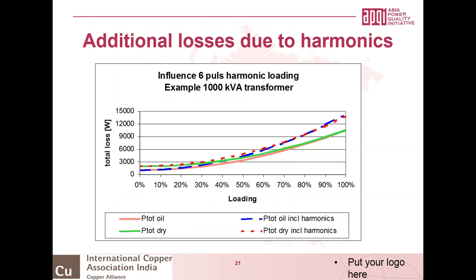so he can take that into account within the design of the transformer. This picture shows you the same situation. On the horizontal axis we have the loading of the transformer, and on the vertical axis the total loss of the transformer. This is a 1 MVA transformer, and we are going to load it once with and once without a 6-pulse harmonic loading. If you don't have any harmonics, I've added a figure for an oil transformer, and also for a dry transformer. Normally a dry transformer has slightly higher losses compared to an oil transformer.